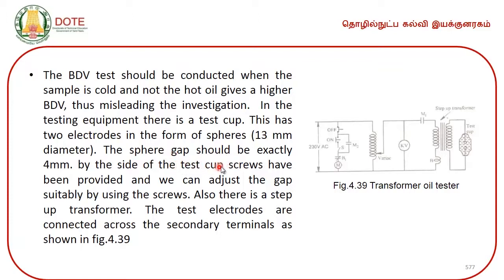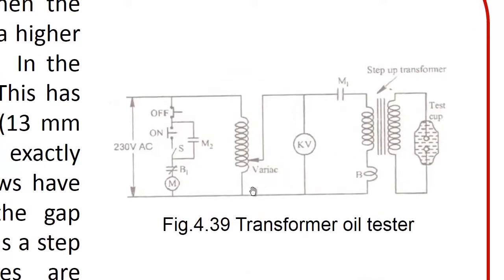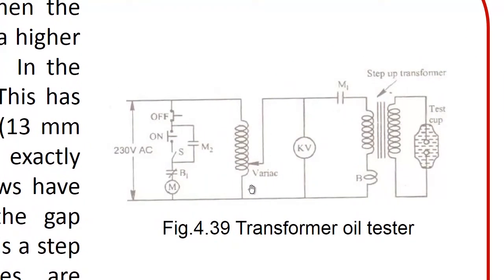By the side of the test cup, screws have been provided and we can adjust the gap suitably by using the screws. Also, there is a step up transformer here. The test electrodes are connected across the secondary terminals as shown in figure 4.39. Let me zoom this in. You can see here, this is the auto transformer variac. This is the primary and this is the secondary. Here is the test cup where the electrodes are placed.